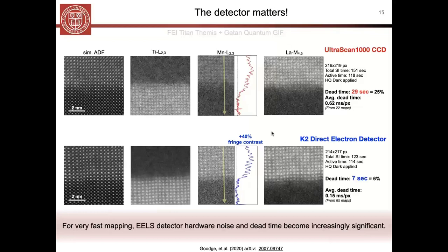If we compare those same statistics for the direct electron detector, the dead time has reduced by a very significant factor, from almost 30 seconds down to 7 seconds. As a total percentage of the map time, we've reduced it by about a factor of 4. So the average dead time per pixel is greatly reduced in the direct detector.